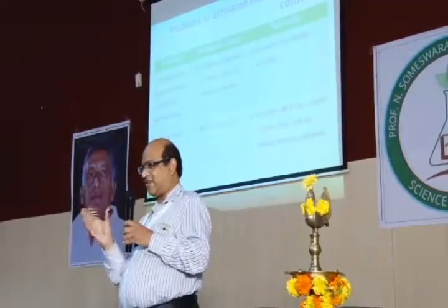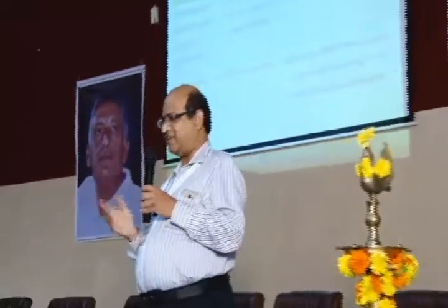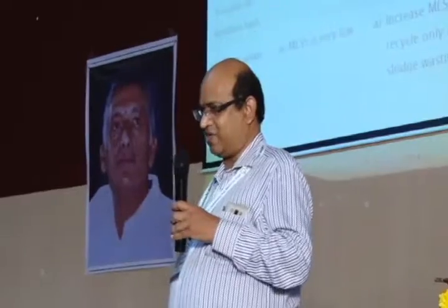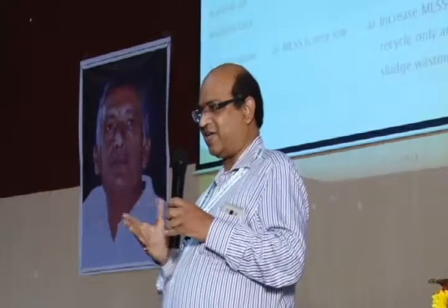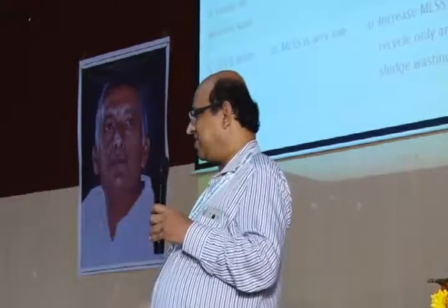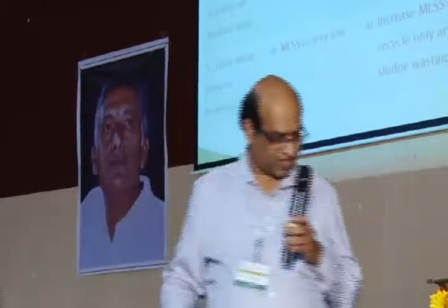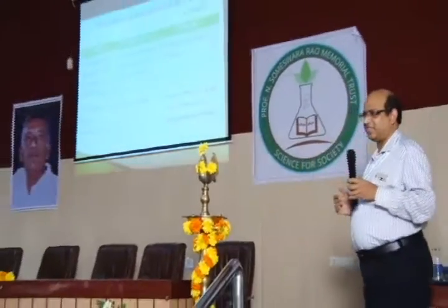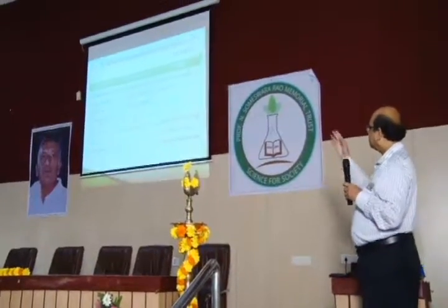If it has a light brownish color, then we can assume that the ASP is working wonderfully. Otherwise, if it is a white color with a lot of foam, or if it is a black color, then we can consider that the required MLSS is still not achieved. So that is the one.